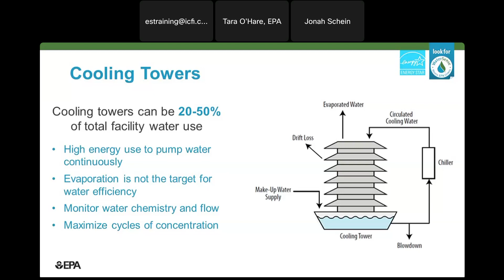A lot of times people will ask, how do I limit the evaporative losses? The answer is you don't want to limit evaporative losses in a cooling tower, because that's what's creating the cooling. If you limit evaporative losses, you may as well not have a cooling tower and just move to something else, because that's what's providing the cooling.